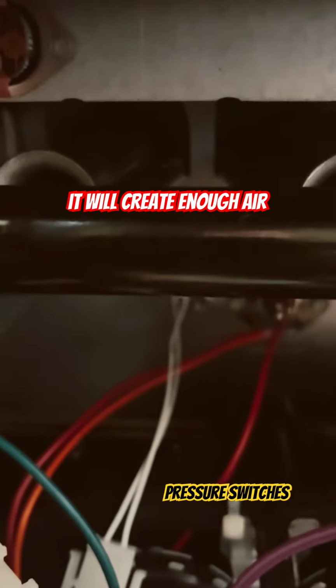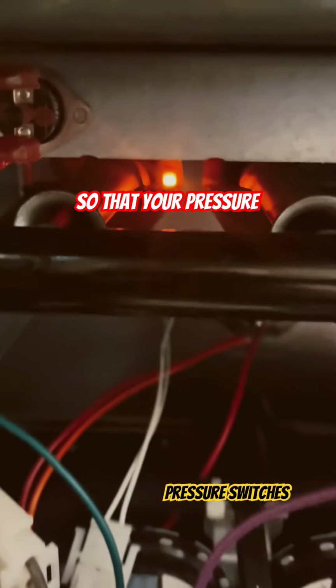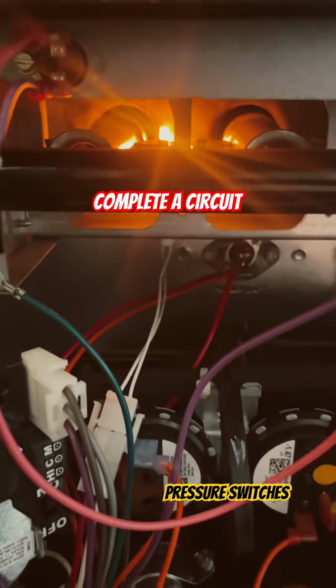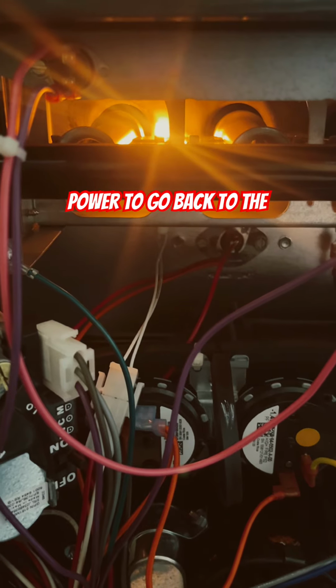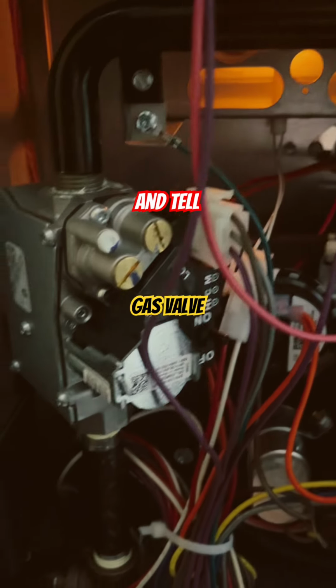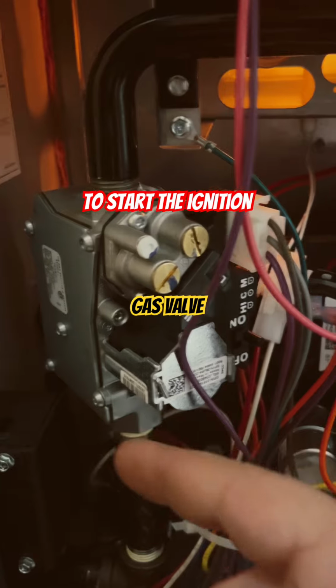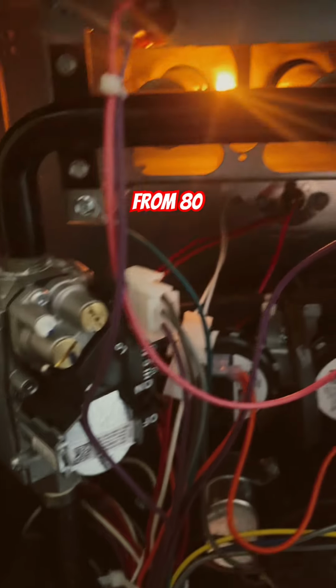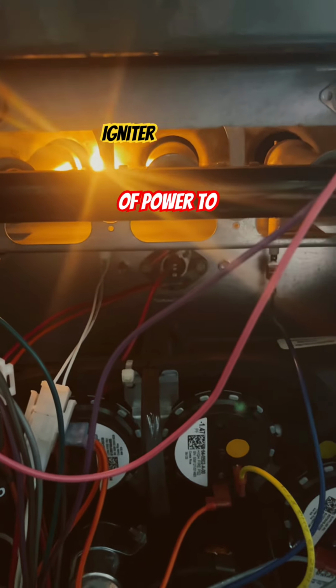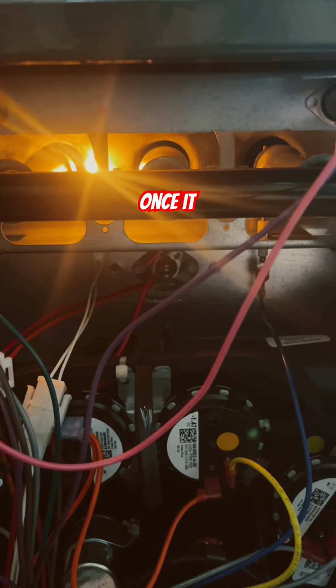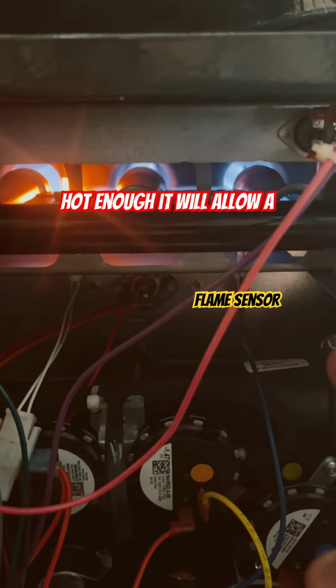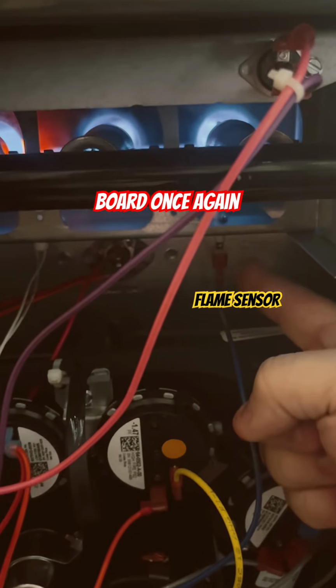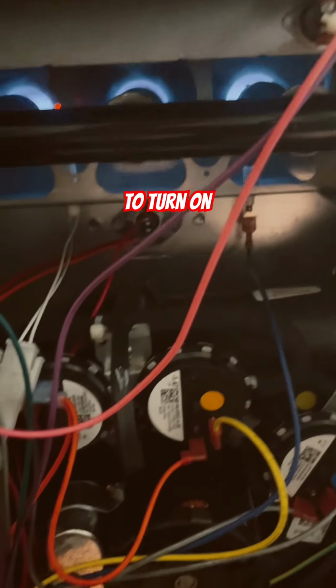It will create enough air pressure so that your pressure switches will then close and complete a circuit that will allow for 24-volt power to go back to the circuit board and tell it to start the ignition sequence, which will then give anywhere from 80 volts to 120 volts of power to your hot surface igniter, and once it gets hot enough, it will allow a signal to go back to the main circuit board once again and tell the gas valve to turn on.